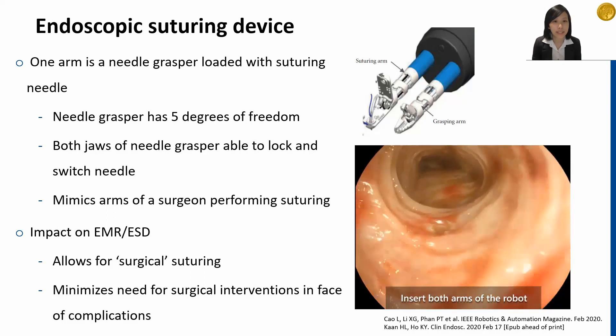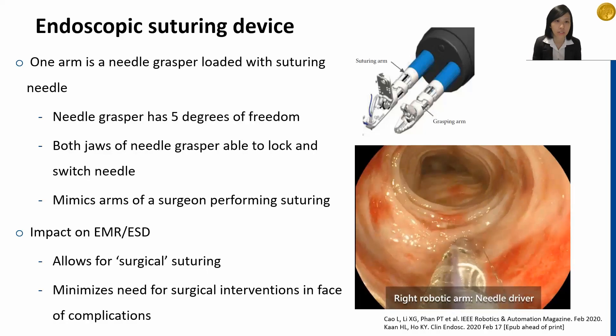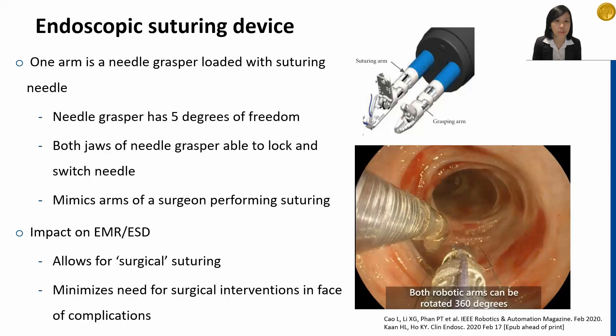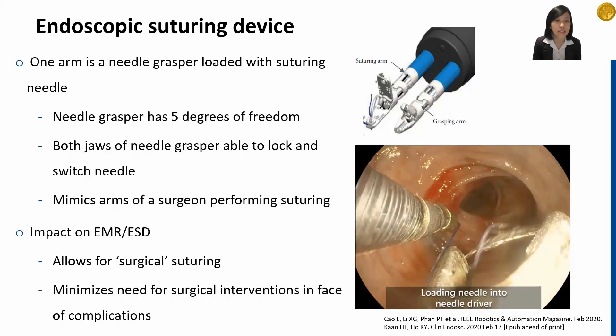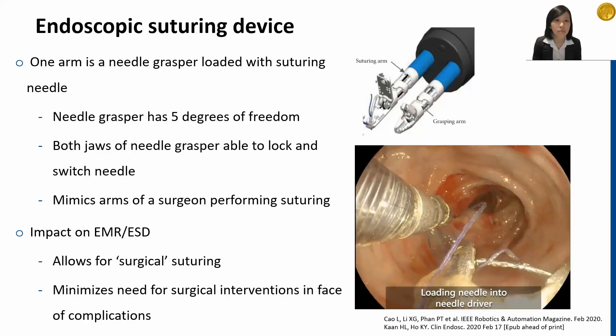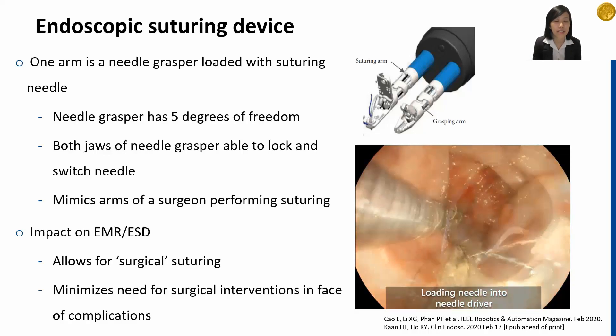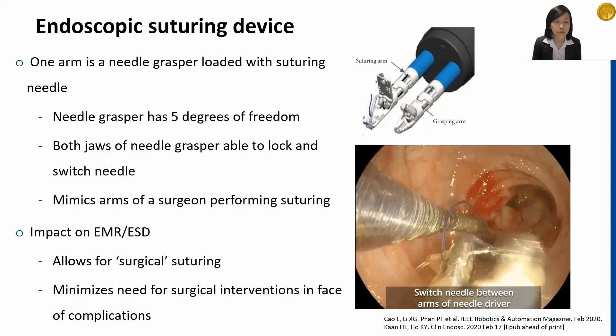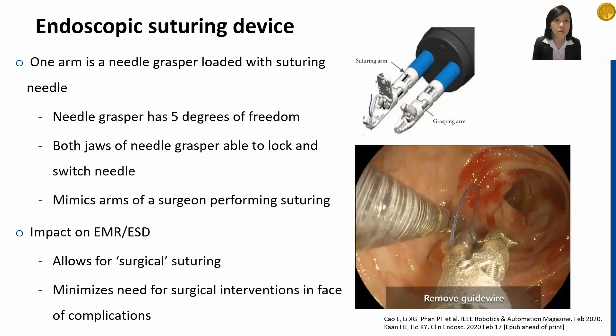In our trial, we inserted the needle driver together with the guide wire and suture needle. Then we inserted the tissue grasper. Both arms can be rotated 360 degrees. We then loaded the needle into the needle driver, which is the right robotic arm. The needle is loaded by pulling on the guide wire externally to align the needle. Once the needle is loaded, it can be switched between the arms of the needle driver and the guide wire is subsequently removed.